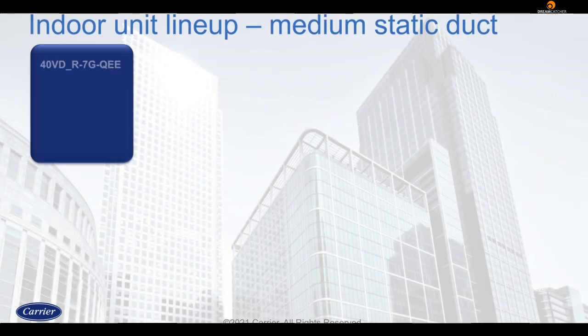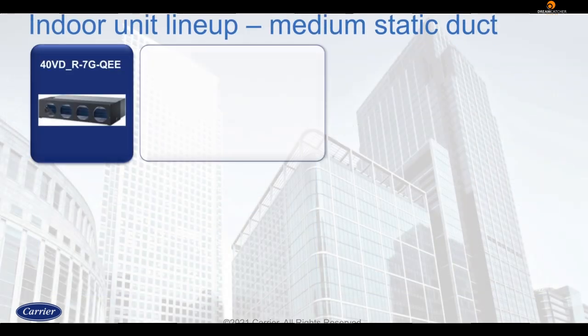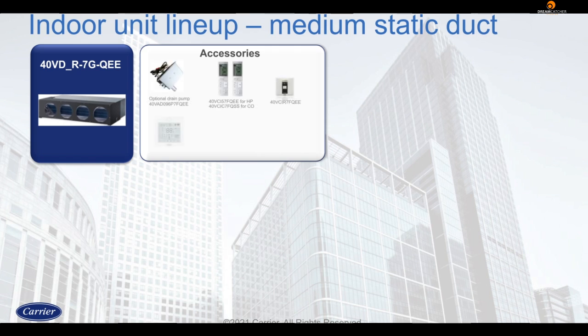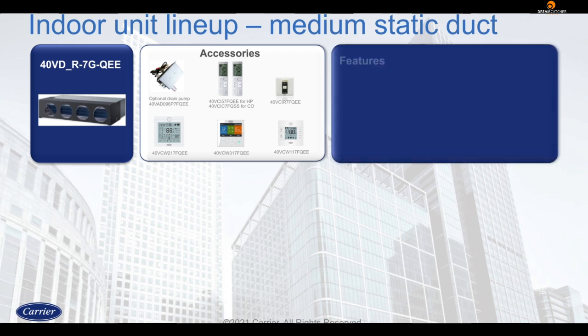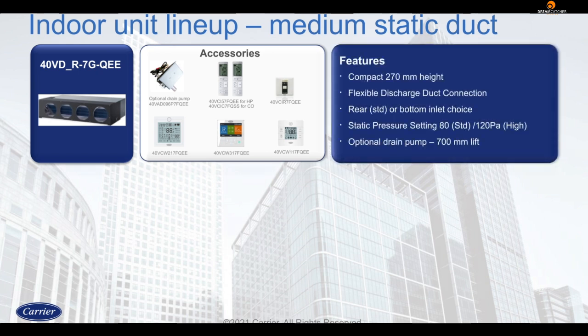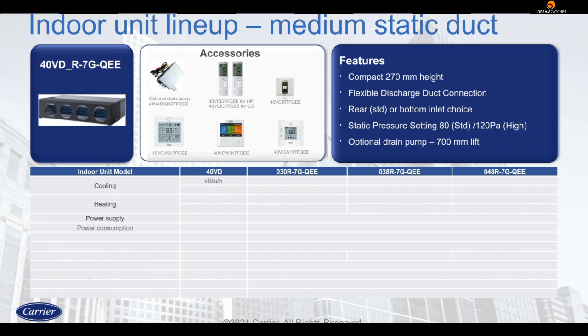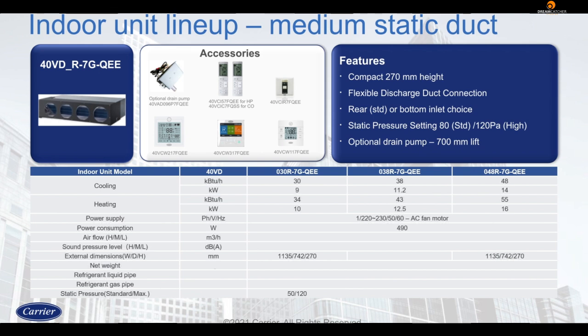The medium static duct has a limited cooling range of 30 to 48 kBTU per hour, but it offers high airflow and higher static pressure compared to the standard static ducted, with a bit of a trade-off in airflow. Keep in mind that the drain pump is not included with it. An order needs to be placed separately for a drain pump.